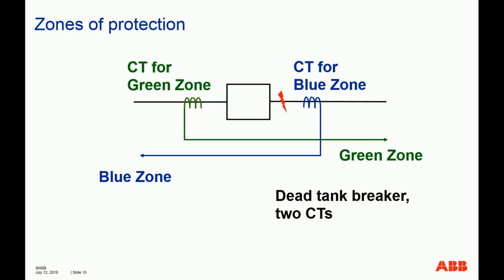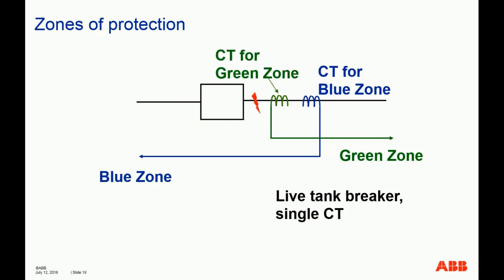So basically, once you see the breaker is open, you can remove the two CTs. By removing those two CTs, for example, imagine the breaker is normally open and you remove these two CTs, then the blue zone will not operate anymore, but the green zone will still operate. So in that case, you will not unnecessarily overtrip, as we call it, the blue zone relay.